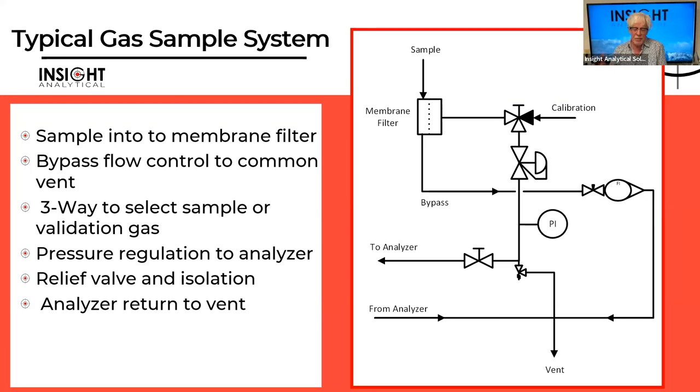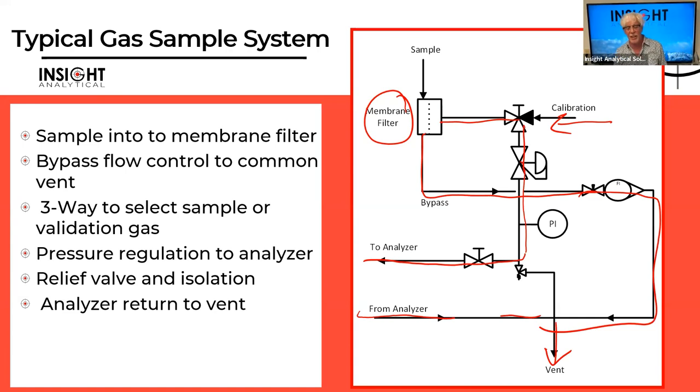If we think about a typical sample system for a gas phase application, specifically around sampling natural gas, this PID may be similar to a lot of the ones that you would see. Sample coming in, going through a membrane filtration unit. We have the filtered side going off to a regulator. We have the opportunity to bring in a calibration gas as well.